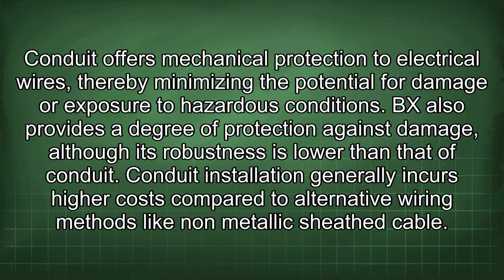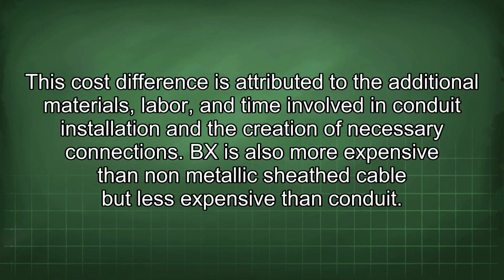Conduit installation generally incurs higher costs compared to alternative wiring methods like non-metallic sheath cable. This cost difference is attributed to the additional materials, labor, and time involved in conduit installation and the creation of necessary connections. BX is also more expensive than non-metallic sheath cable but less expensive than conduit.